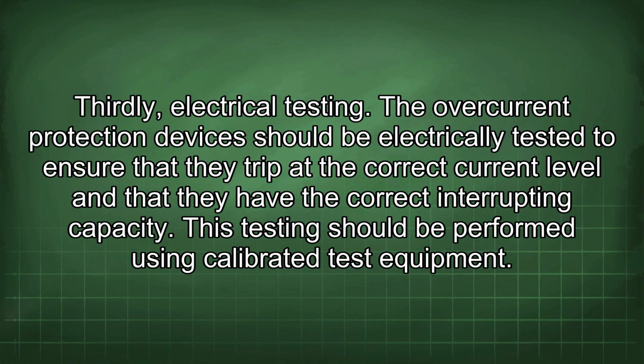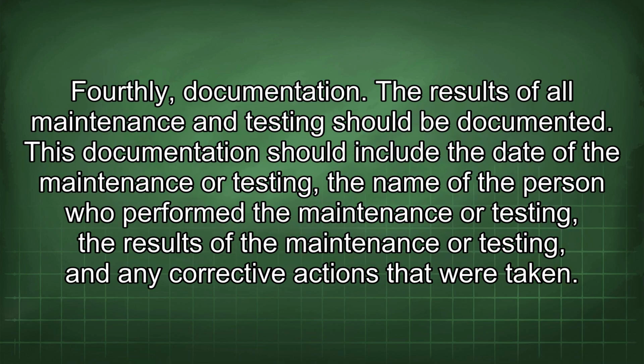Thirdly, electrical testing. The overcurrent protection devices should be electrically tested to ensure that they trip at the correct current level and that they have the correct interrupting capacity. This testing should be performed using calibrated test equipment. Fourthly, documentation. The results of all maintenance and testing should be documented. This documentation should include the date of the maintenance or testing, the name of the person who performed the maintenance or testing, the results of the maintenance or testing, and any corrective actions that were taken.